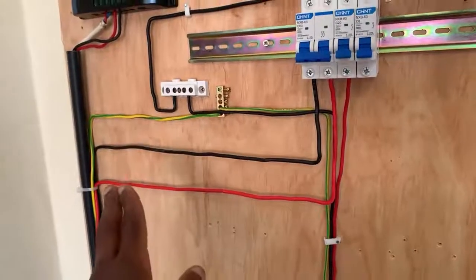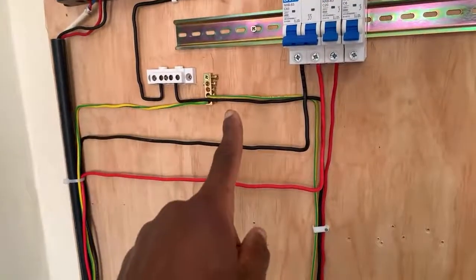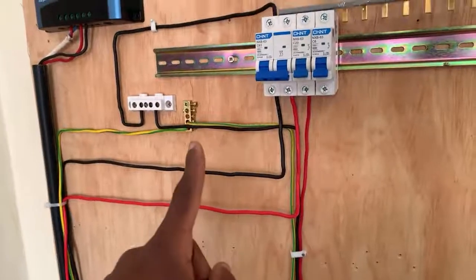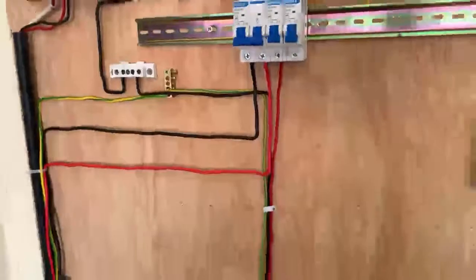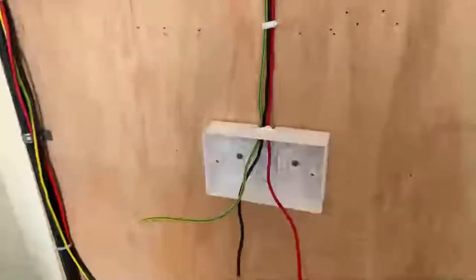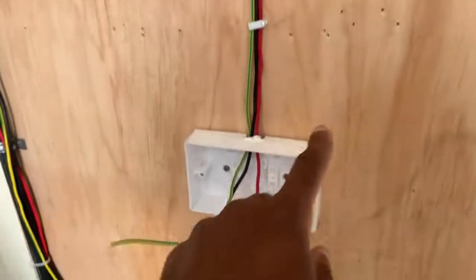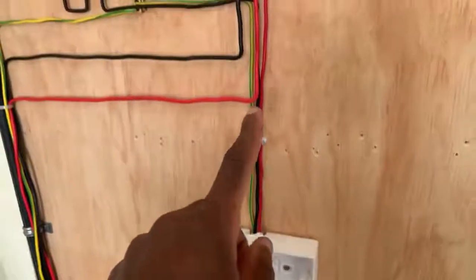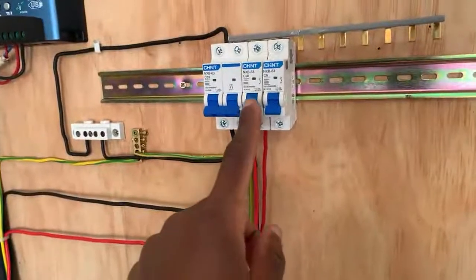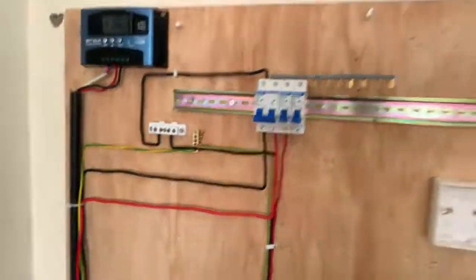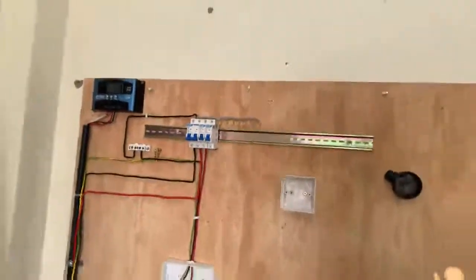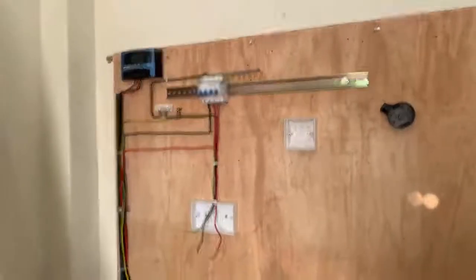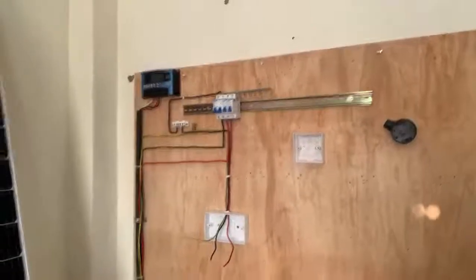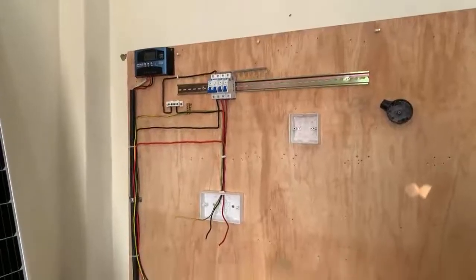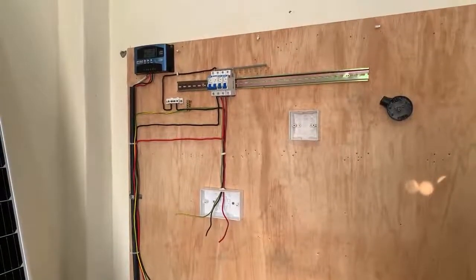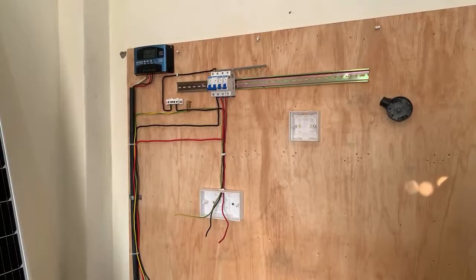Remember, the earth bar from the meter box comes all the way to the consumer unit to the earth bar, with no interruption. Then the phase from the socket goes all the way to this MCB. I'm using a 20 amp MCB since this socket is just for very light loads.